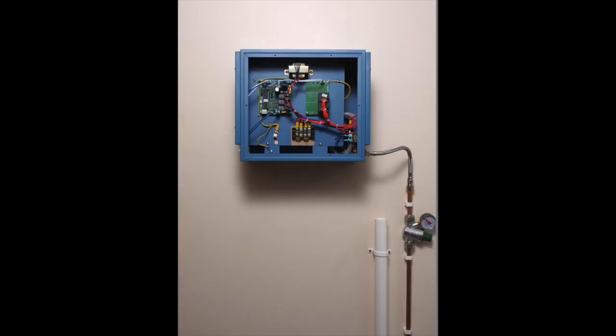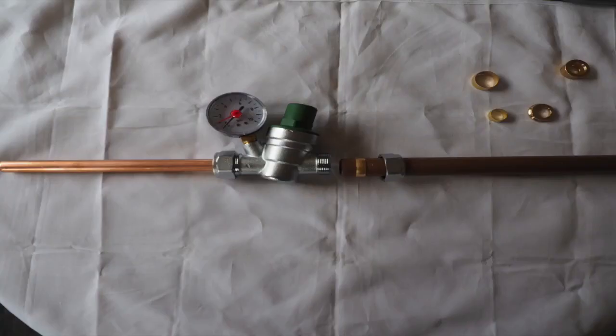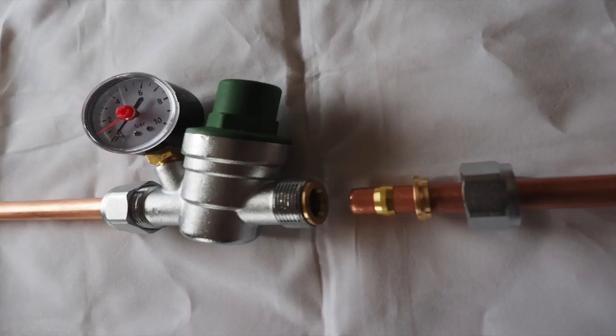In this example, we have used one with an isolation valve built in. There should be a pressure reducing valve in front of the steam generator on the water supply. This should be set at maximum of one bar. Set the pressure when the water is flowing. Most pressure reducing valves will come with a 22 millimeter or 15 millimeter conversion kit.